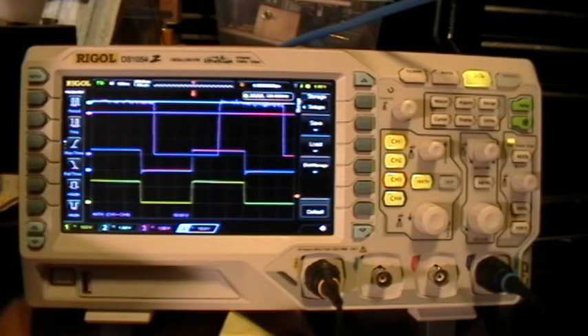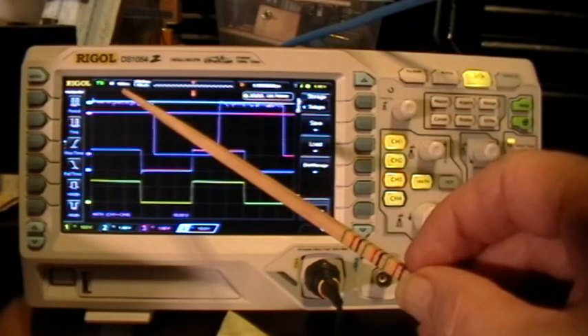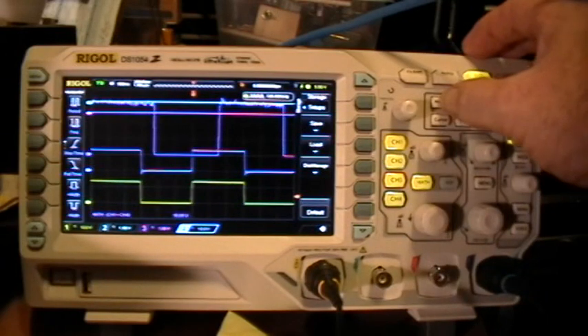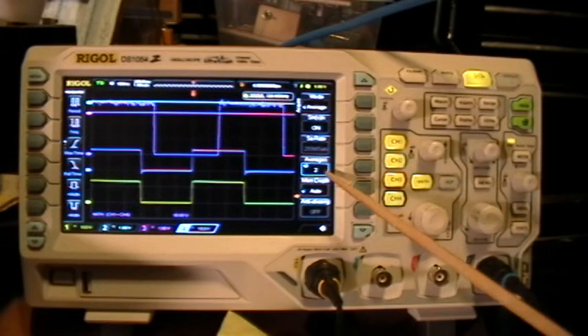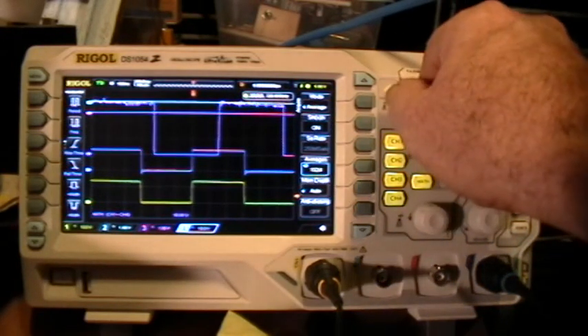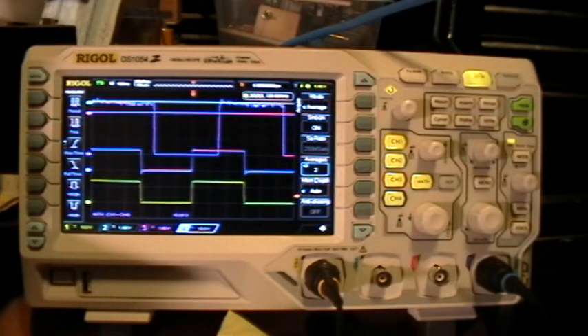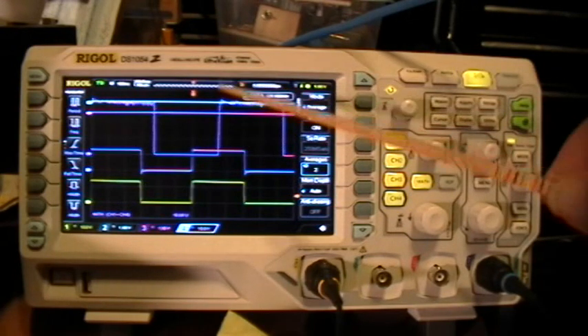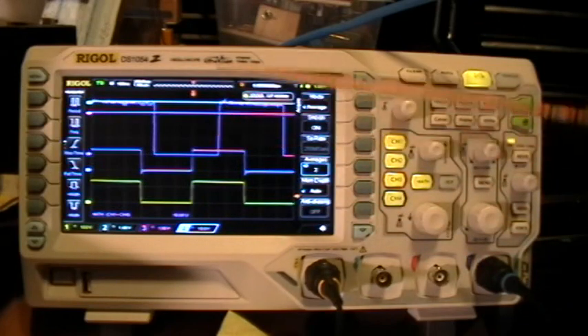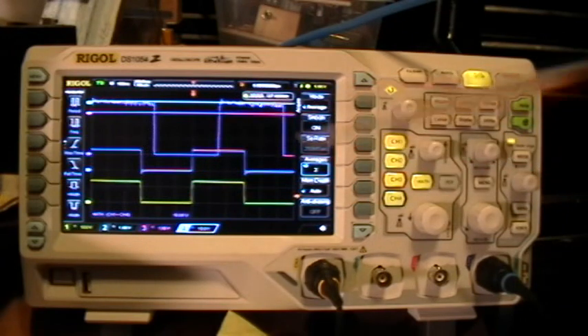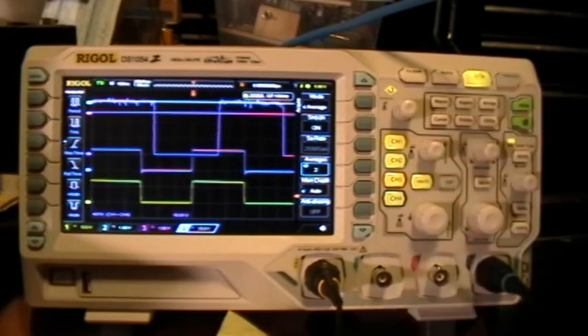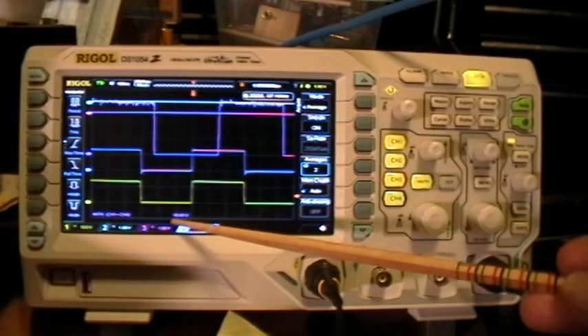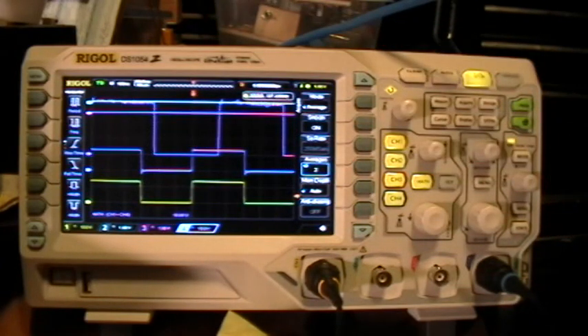Let's take a look at the conditions for the math error bug: 500 nanosecond time base, 500 nanoseconds per division, acquire menu average, two averages or more, doesn't matter how many averages but you should be in the average acquisition mode, and all four channels on. Sometimes maybe only three channels on, but the two channels multiplied, the scales, vertical scales don't matter. We're looking at 50 units per division on the math trace there.